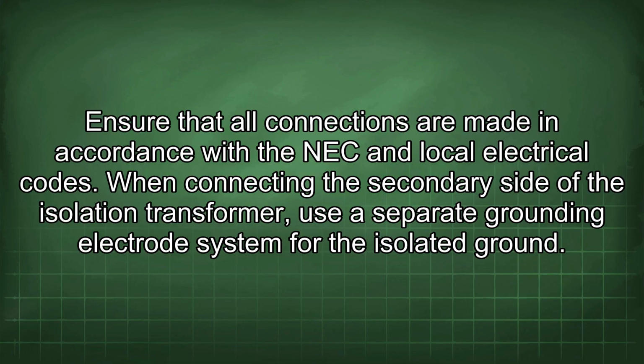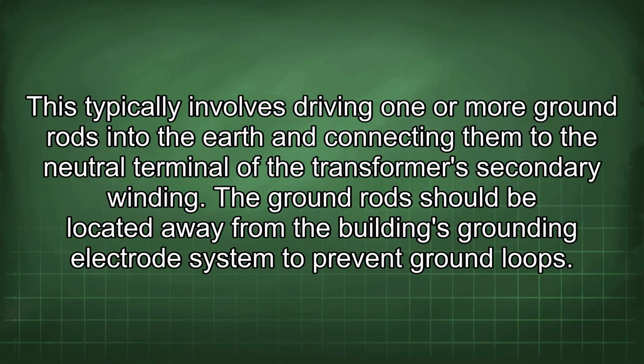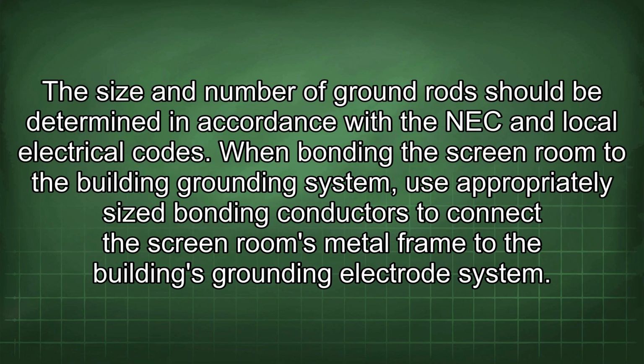When connecting the secondary side of the isolation transformer, use a separate grounding electrode system for the isolated ground. This typically involves driving one or more ground rods into the earth and connecting them to the neutral terminal of the transformer's secondary winding. The ground rod should be located away from the building's grounding electrode system to prevent ground loops. The size and number of ground rods should be determined in accordance with the NEC and local electrical codes.